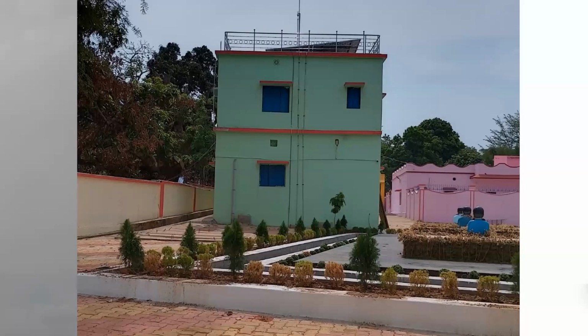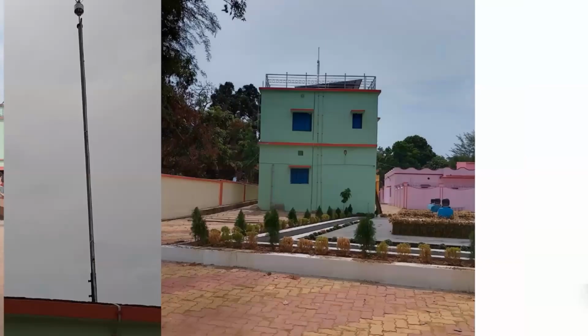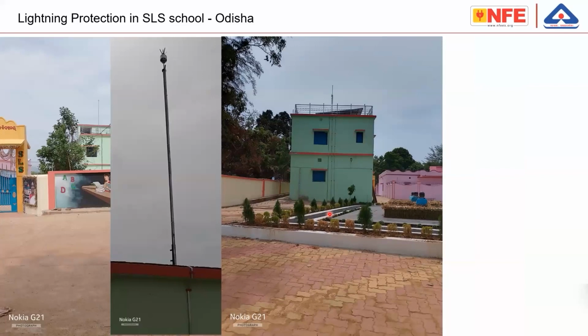As a result, the amount of current flow through each of the down conductors is reduced to a low level, and its effects are thus reduced. So one down conductor like this particular installation is really dangerous. Even the standard says you have to keep at least 3 meters away from a down conductor. Please note that that is applicable to a building where a lightning protection as per 62305 is installed.